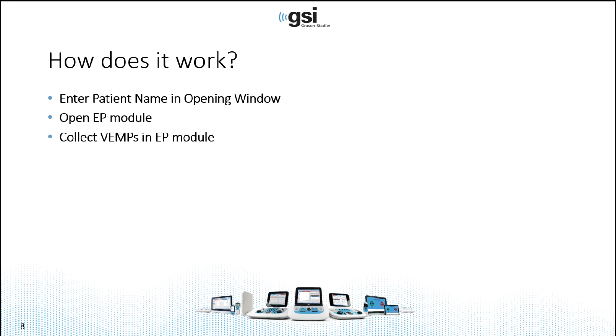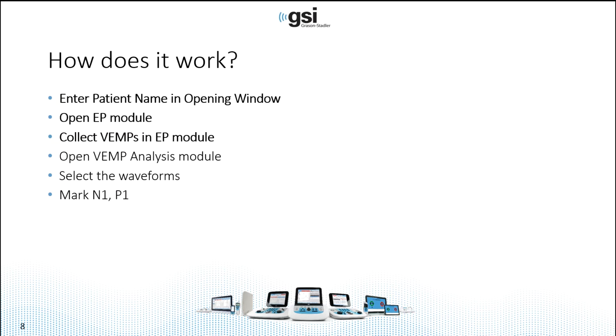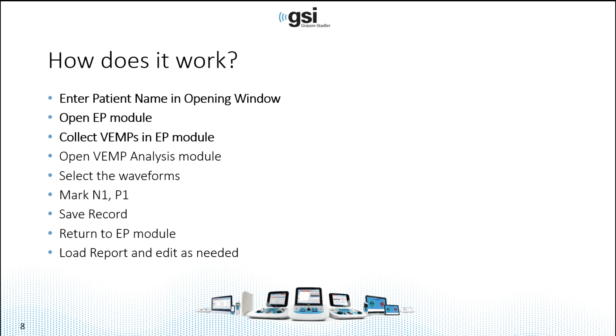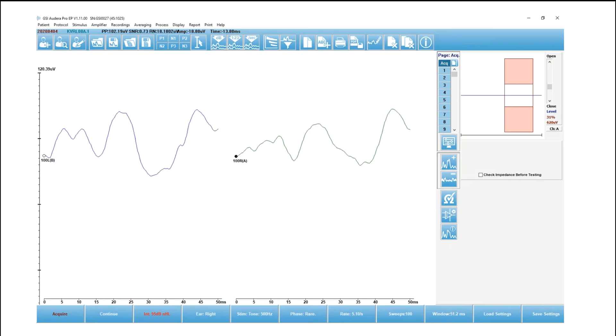So how does it work? You're going to launch the Audera Pro software and enter the patient name from the opening screen. Then you're going to launch the EP module and collect your VEMPs. Once you're done, open the analysis module, select the waveforms you want to analyze, mark the N1 and P1, save the record, go back to the EP module, and load the report. Then you're good to go for editing, etc. So that's the general flow.